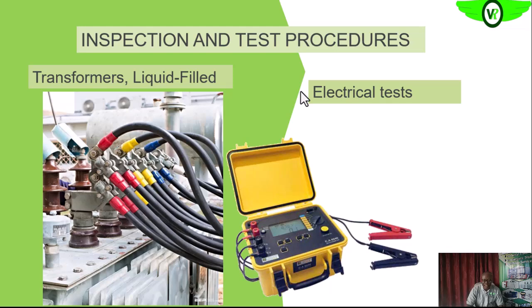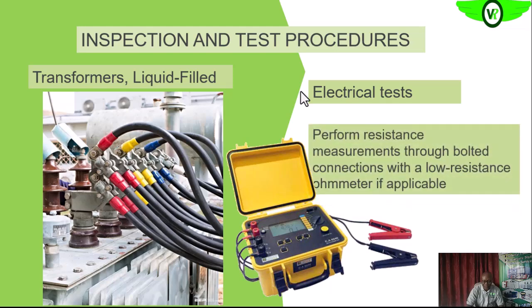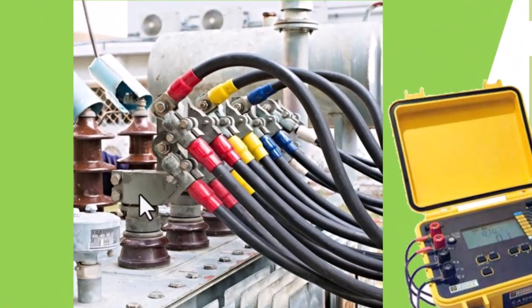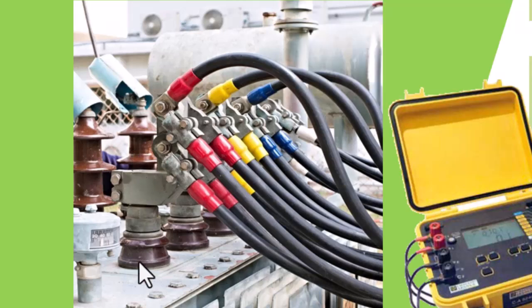So for the electrical test, like we said earlier, there are a few of them that we need to carry out on the transformer. So the first, on the bolted connections, we want to carry out resistance tests. We can use any low resistance meter, milliohm meter, place one of the probes here, and then probe this end. If we do it as such, that will give us the resistances between these terminal lugs and the conducting part that is feeding the transformer winding.